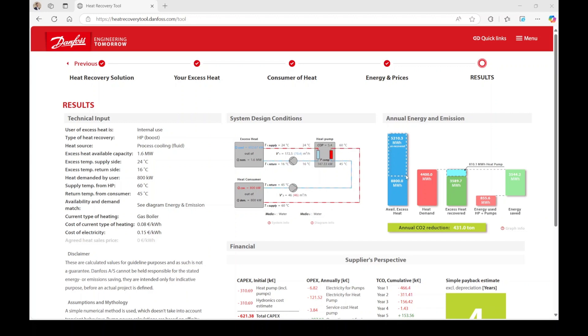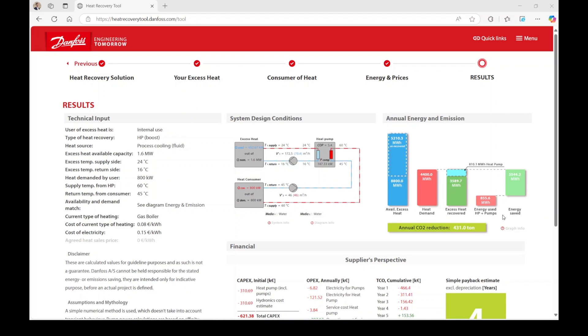Conversely, if there isn't enough heat available to fully meet your demand, there will be an uncovered portion, meaning your current heating system will still be necessary, albeit with a reduced load. In relation to the recovered heat, you can view the energy required for the heat pump and pumps. The difference between the energy used by the heat pump and pumps and the recovered heat offers an initial overview of the potential energy savings achieved through heat recovery and reuse.